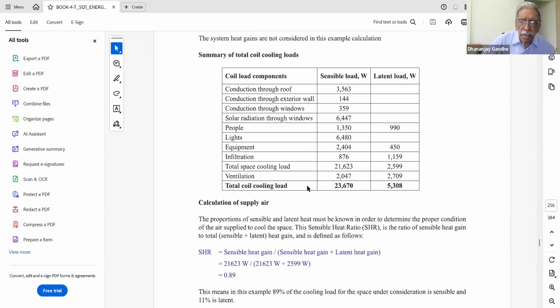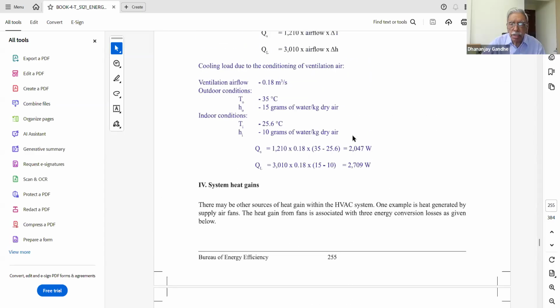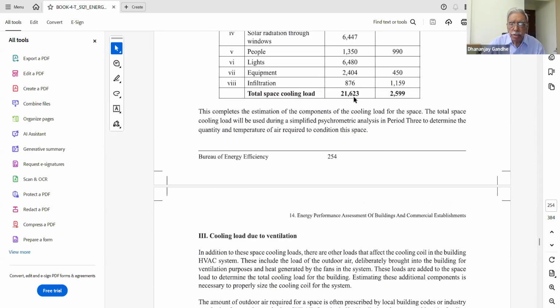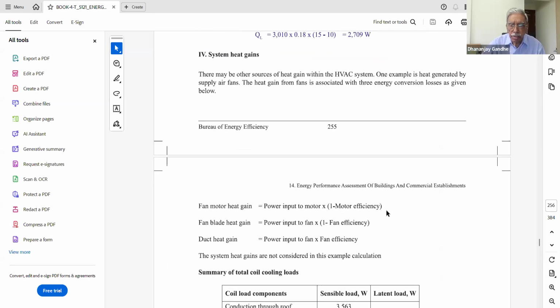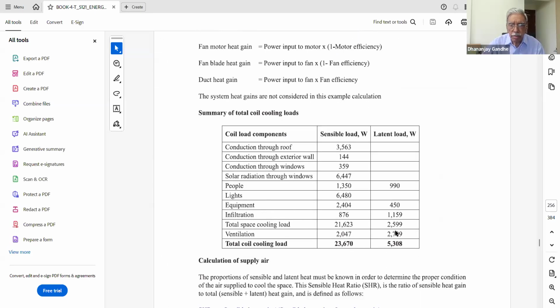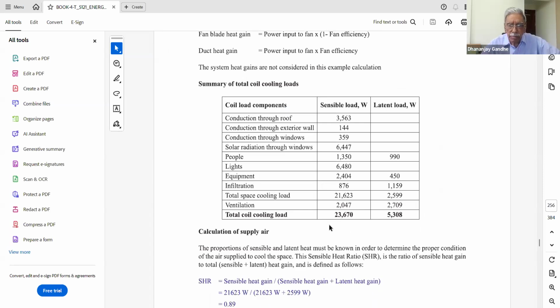And to the summary table, they will also add the ventilation loads. These are the earlier figures, 21,623, that you can see, and 2,599 latent heat load. These figures are carried forward here in the summary table. Add the ventilation load for the fans, which is calculated here, 2047 and 2709. So these are added together.